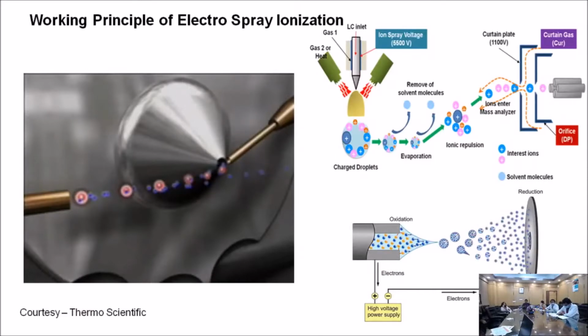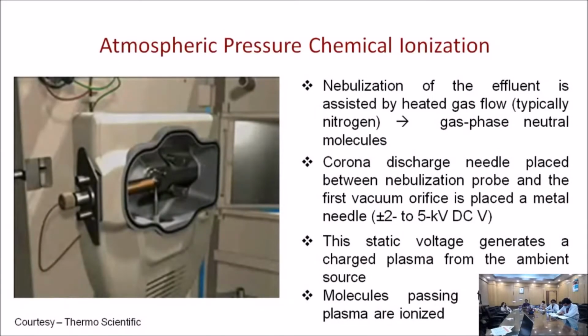Let me explain another principle, atmospheric pressure chemical ionization. This is useful for nonpolar compounds. Instead of being infused directly, the nonpolar compounds are evaporated by a heated nebulizer. There is a corona needle in the heated nebulizer that constantly generates a charged plasma, and that plasma ionizes the gas molecules. I'll show you this video of the mechanism of atmospheric pressure chemical ionization.